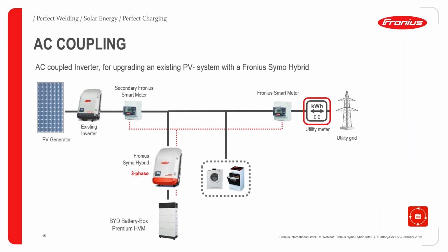You could also do AC coupling. You don't have to have PV connected to the hybrid inverter itself. You can just use it as an AC coupled battery charging system. If you've got an existing PV three-phase inverter there, or even a single phase, but obviously a three-phase site, you can connect that in an AC coupled mode, and then it will charge from this PV inverter. One thing to note is that if you do this, then when the inverter goes into backup mode, it runs at a 53 Hertz AC signal, in order to kick off any AC coupled inverters because it can't control them in backup mode. But in normal grid connect mode, obviously it can.